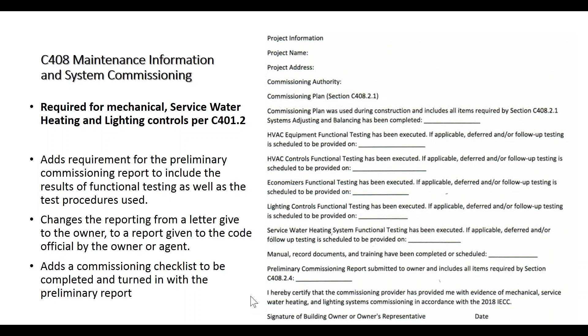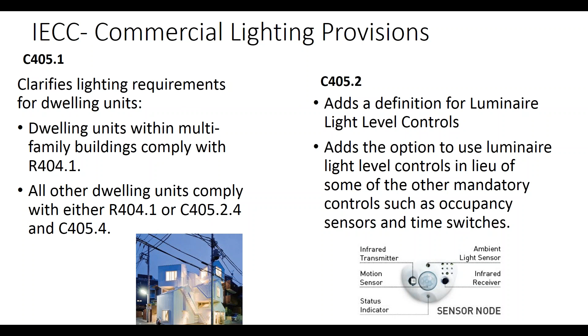When it comes to lighting, some changes, just clarifying that when you have dwelling units in apartment buildings, you comply with the residential code, and then everything else can comply with the residential code or the commercial code, you have your choices. They brought in this new definition for luminaire light level controls because they brought in the option that you can use luminaire light level controls in lieu of occupancy sensors or time switches in certain places. So luminaire light level control is like this light level control that senses all of the light, not just the outside light, but the other lights in the space, and lets you keep the lights to a certain level. And so that is now an additional option in the code.